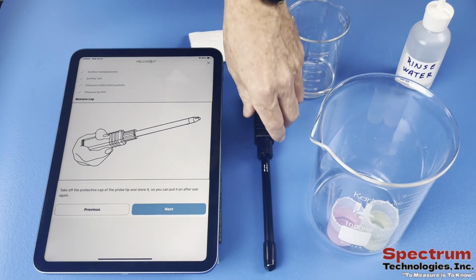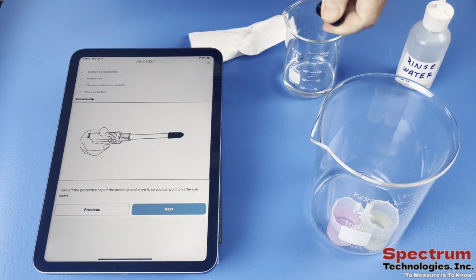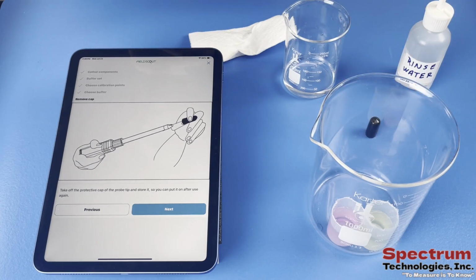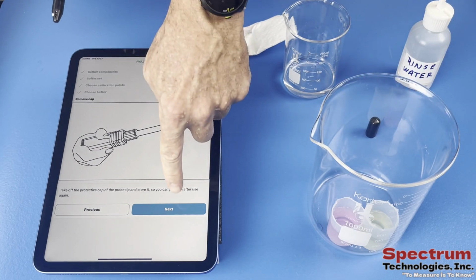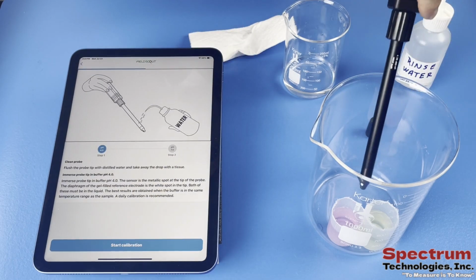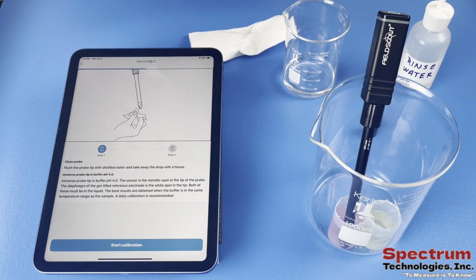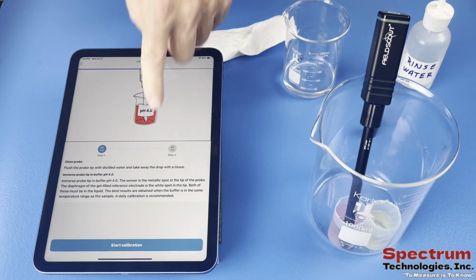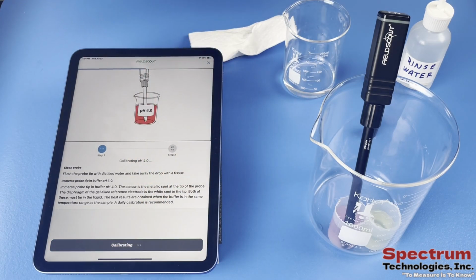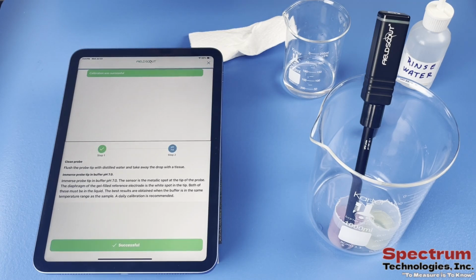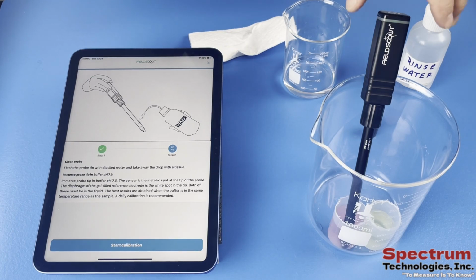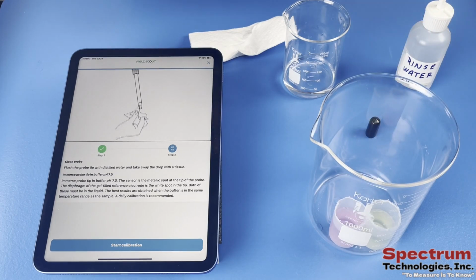Remove the cap from the sensor tip. Tap Next again and place the probe in pH 4 buffer. Make sure the sensor is fully submerged in the buffer during each step. Tap Start Calibration and wait. This may take a moment to complete. Once complete, the blue dot next to pH 4 will turn green, confirming success. Remove the probe, rinse it with clean water, and gently dry.